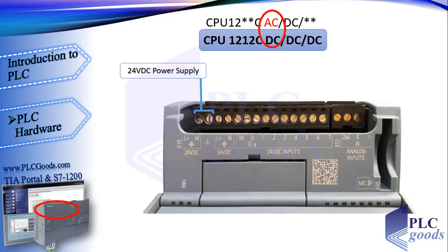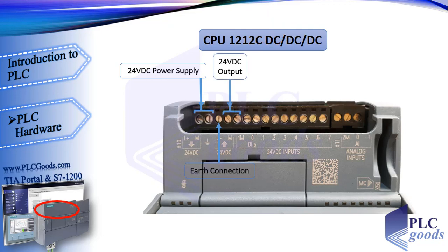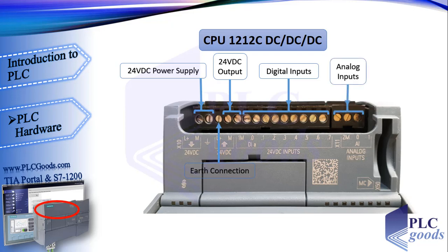For safety, the next terminal connects the PLC body to earth. This CPU also provides a 24-volt DC output to supply sensors or other instruments connected to it. Next are the digital inputs — a digital input has only two states: on or off. The first terminal is common for all eight digital inputs, which operate at 24 volts. The last three terminals are for analog inputs.